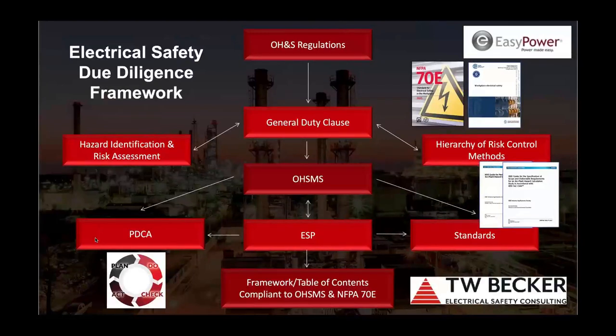So we've got the OH&S regulations, the general duty clause: identify all hazards, eliminate or implement controls to reduce risk. So hazard ID and risk assessment on the left, the hierarchy of risk control methods on the right, the occupational health and safety management system, and ultimately the electrical safety program underneath it, the plan, do, check, act philosophy on the bottom left, and then the standards, 70E, Z462, and for the calculations for 208 volt to 15 kV three phase, IEEE 1584, and this 1584.1 supplemental guide that I really encourage you to purchase and have available to identify a quality study and a quality report.